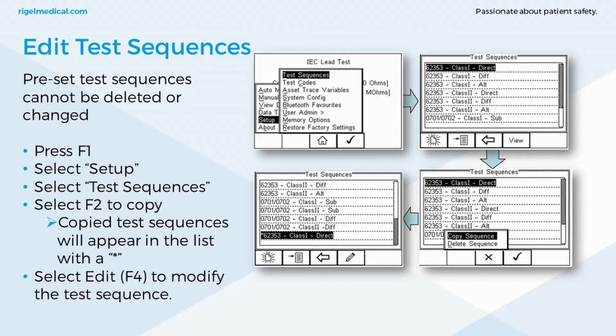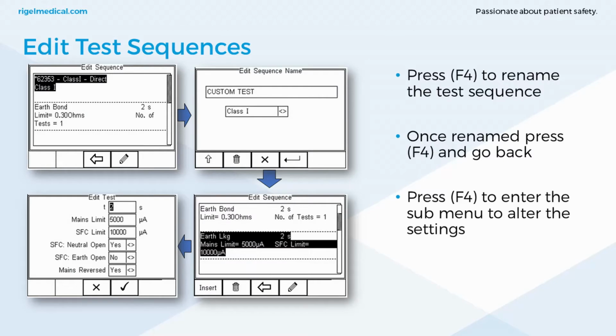Now to edit test sequences, the easiest way to do this is to go into a test sequence, pick the test that closely resembles the test that you want to create, and then copy that test sequence, and that will make a copy of that with a star next to it, and then from there you can use the edit key to edit that test sequence, and it will just be in that the original 62353 configuration, but you can then edit it to be customized. So here you can rename the test sequence. Once renamed, you can press F4 and go back. Press F4 to enter the sub-menu to alter the settings. So not only can you add custom tests, you can change the leakage limits, you can change the duration of the tests to make it more customizable for your testing needs.